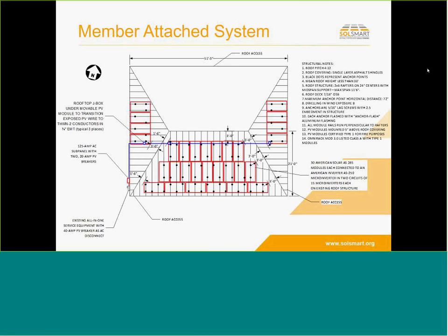A microinverter, for instance, which is of course going to be on the roof, does have plug connectors, and those plug connectors can comply with the disconnect requirements. Products on the market like Enphase, the connectors are actually listed with their device as disconnects. Are you unplugging the plug as a disconnect then? Correct. The Enphase microinverter, it is a disconnect. The code allows connectors to be used as disconnects as long as they've been listed for the application in that situation.